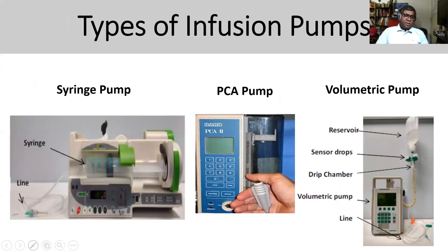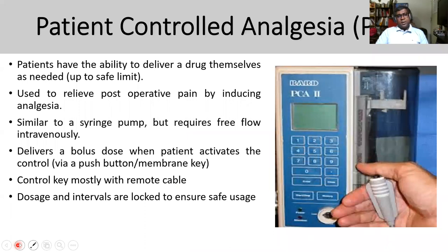The types of infusion you're going to see are syringe pumps with a syringe and tubing line, and PCA pumps — similar to syringe pumps with a start/stop switch. Volumetric pumps have a reservoir bag, drop sensor, drip chamber, and the line. A PCA pump is normally used for patient-controlled drug management — the patient uses a push button to self-administer drugs with a safely controlled dosage.